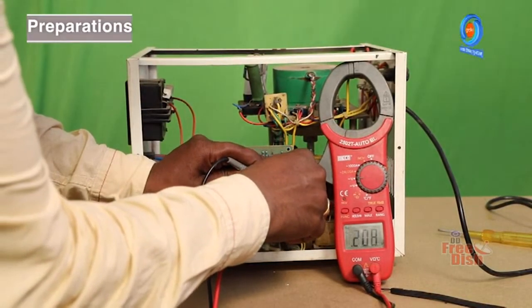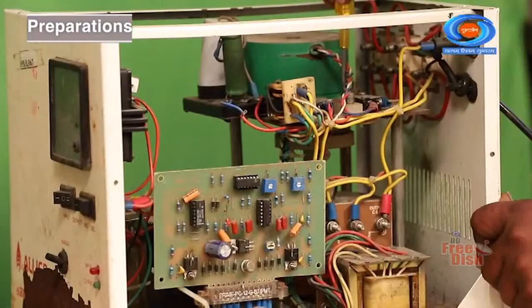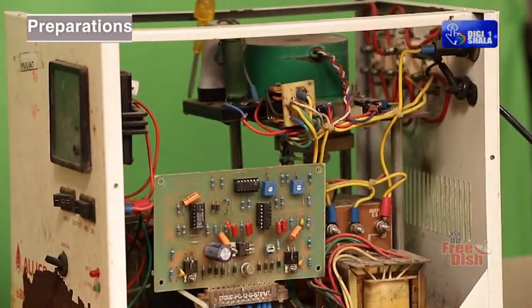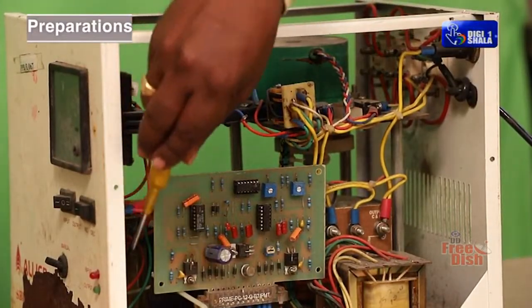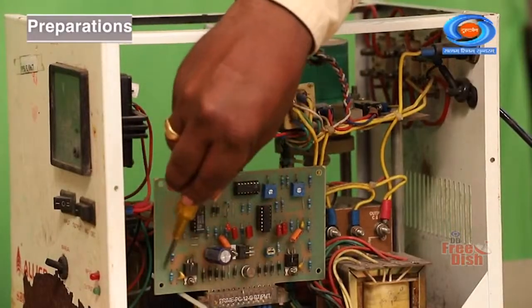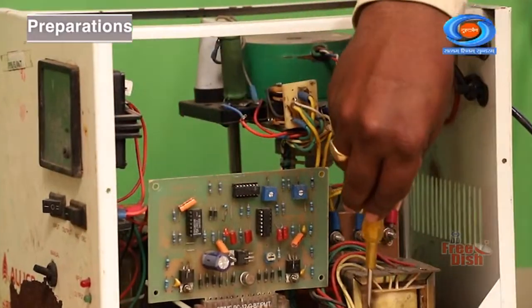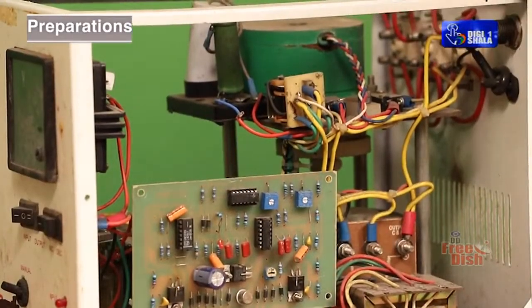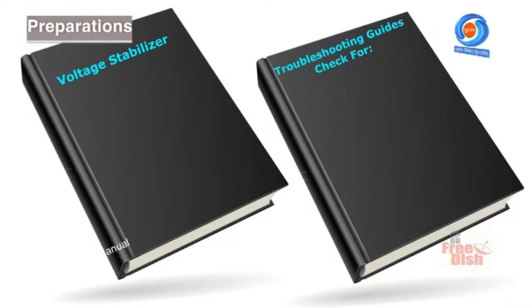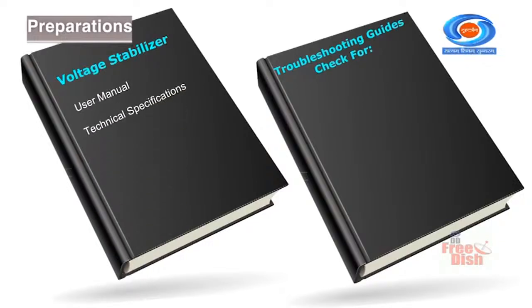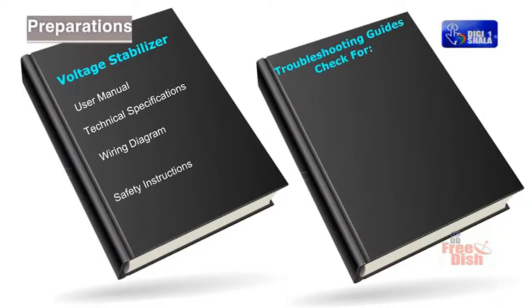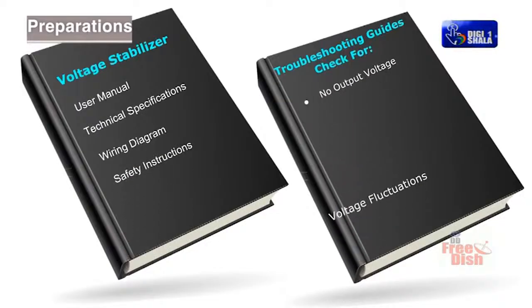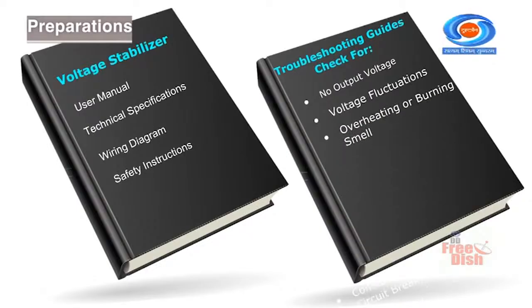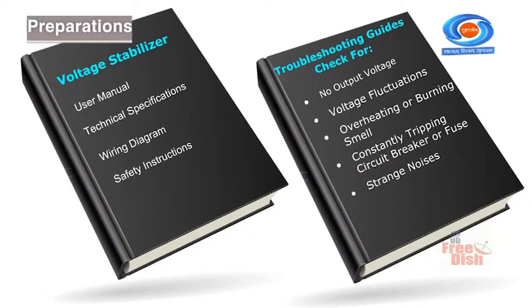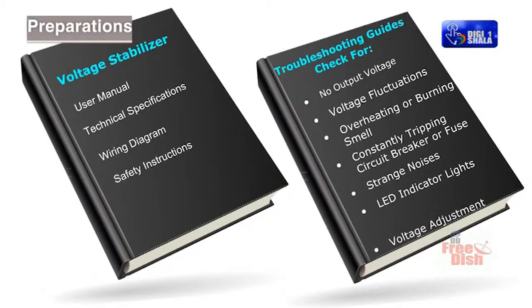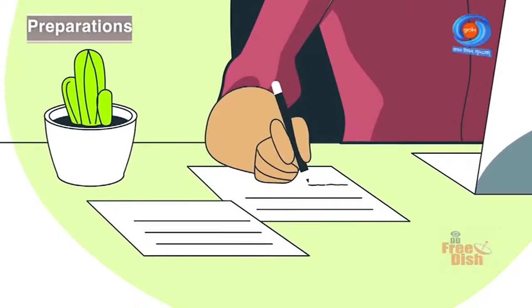If it is a healthy circuit, it will show some resistance reading. Analyze the status of the circuit by the meter's reading. If the stabilizer is without short circuit fault, connect it to the supply mains and switch on. Based on the symptoms observed during the testing, identify the potential fault areas. Refer to the troubleshooting guide for common issues associated with the stabilizer. Some common faults in voltage stabilizers include faulty voltage regulators, defective capacitors, open or short circuits, or overheating components.